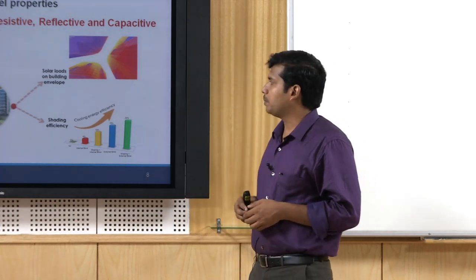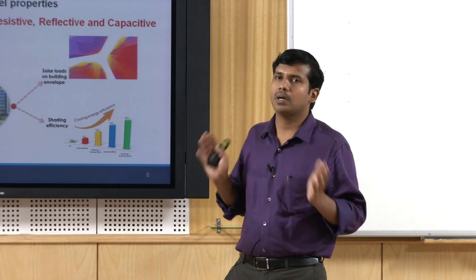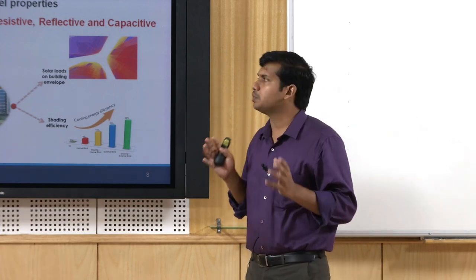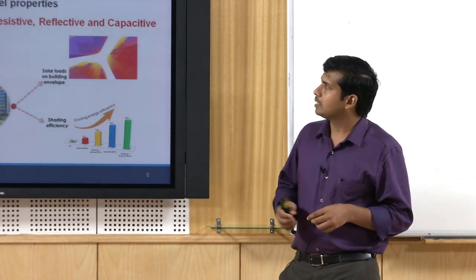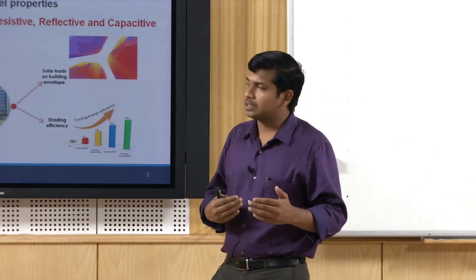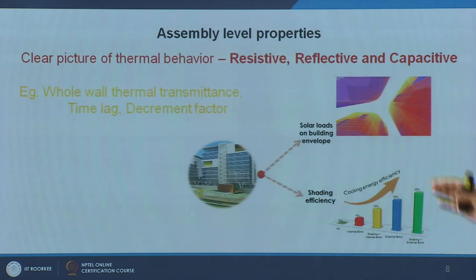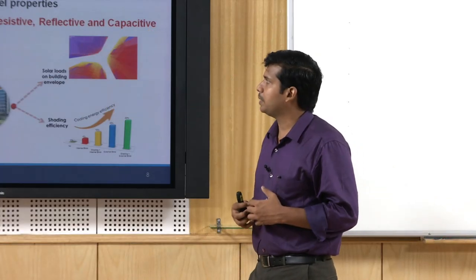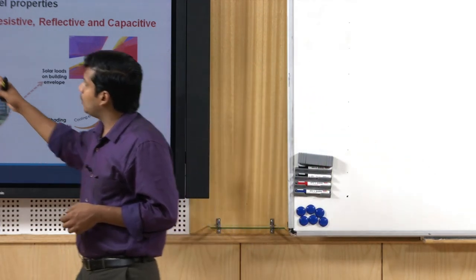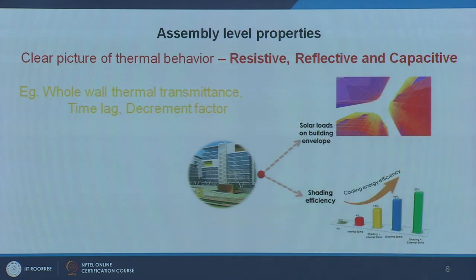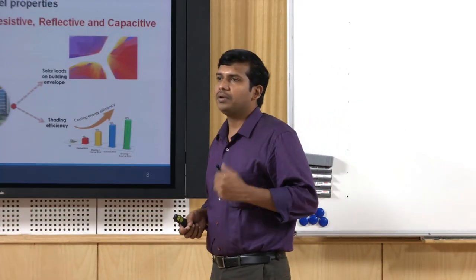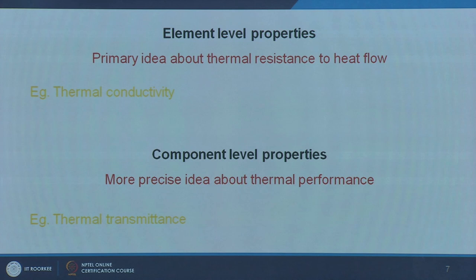For example, thermal transmittance of a 230 mm brick wall or a 200 mm thick solid concrete wall gives a better idea than element level performance about heat flow. The next level is assembly level properties — say a window frame and wall assembly — and what happens to the overall performance of that wall system. This is more critical and gives a very clear picture about all three types of heat transfer: resistive properties, reflective properties, and the capacitive or heat-storing capacity of the whole assembly.